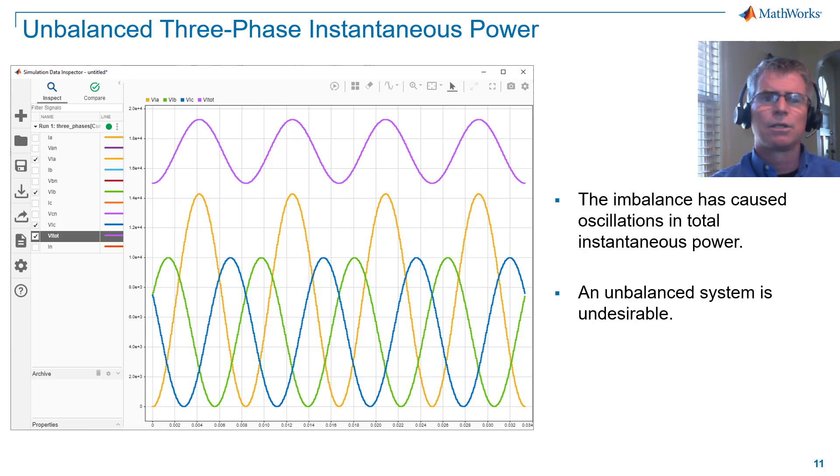The imbalance has caused oscillations in total instantaneous power. An unbalanced system is undesirable for a number of reasons. The oscillation in total delivered power is one of those reasons. For example, if we're driving a three-phase motor, the imbalance would cause mechanical oscillations and uneven heating of the motor currents.